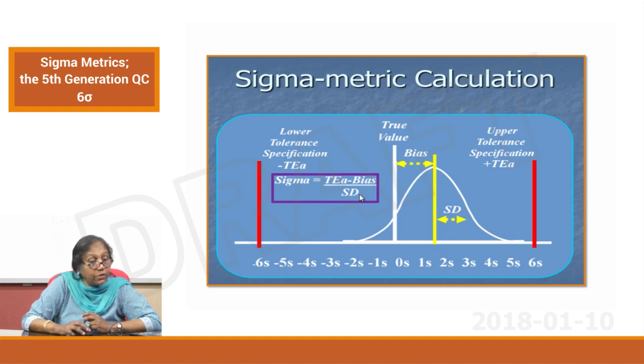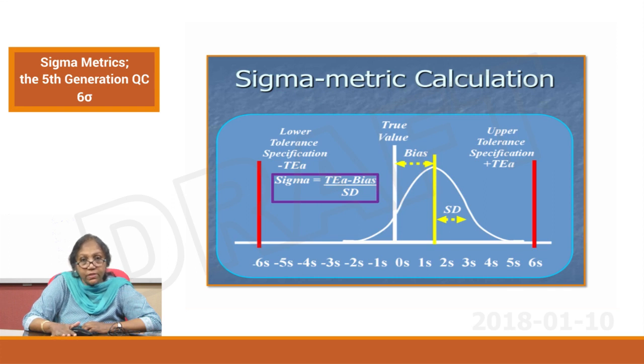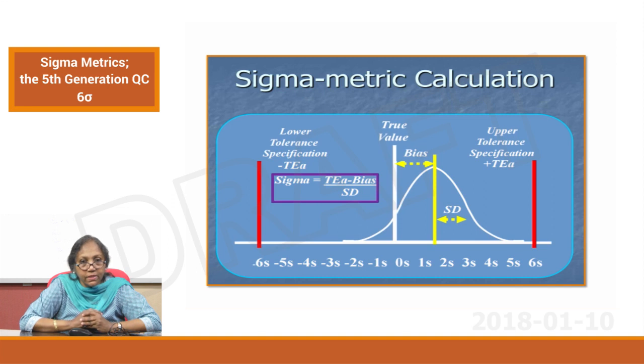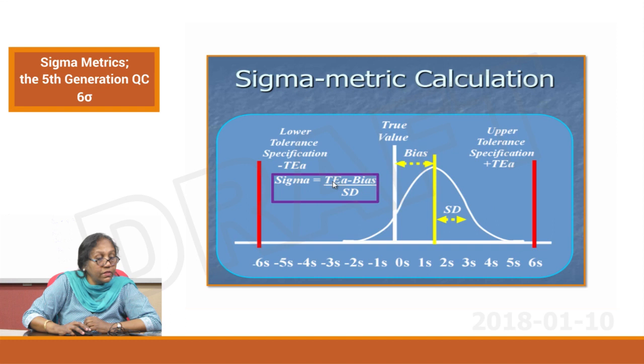You really cannot go forward from your LJ unless you have some kind of peer group support. Get your peer group data. If your peer group is there, you can calculate the bias, and you can take the SD and CV from your LJs — then it is really easy to calculate. All these calculations can very easily be done on the QC software on the Westgard website. You just put in the numbers, define where you are getting your TEA from — CLIA, BV values — and you will understand your performance. Sigma equals total allowable error minus bias, divided by standard deviation.